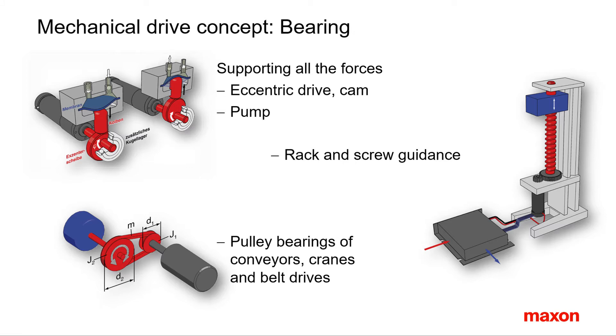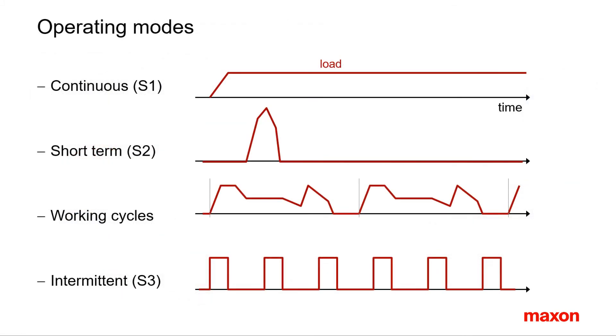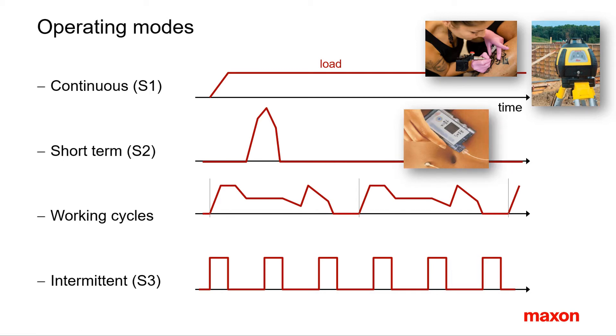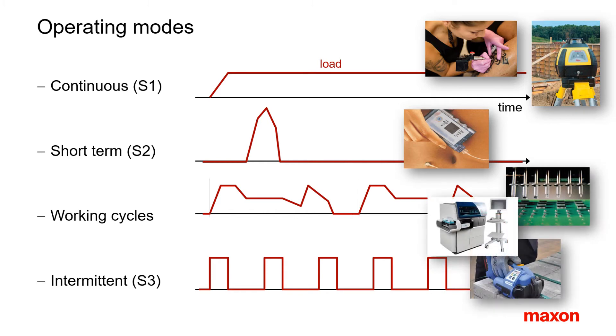The orientation with respect to gravity might also be a valuable information. The required motion can lead to different load scenarios. Basically, four operation modes can be differentiated: continuous operation, where the drive accelerates once and moves with a constant load for a long period — examples are laser beam deflection or a tattoo gun; short-term operation, with intense load during a short period followed by a very long standstill — an example is an insulin pump; cyclic operation, characterized by a relatively short variable load profile continuously repeated — typical examples include pick and place; and on-off operation, a special case of cyclic operation.